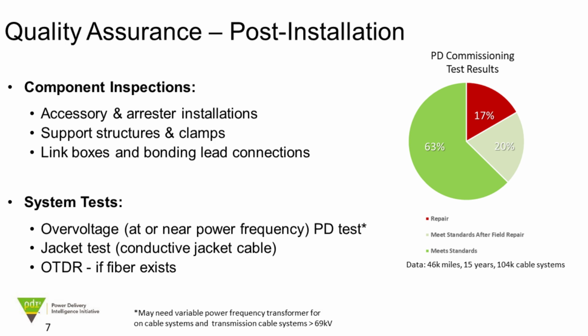Link boxes and bonding leads for cross-bonded and single-point bonded systems. This is typically a transmission application. You need to make sure that those connections are proper. Can't tell you how many times that even after a test is complete and everything looks to be properly installed from a dielectric standpoint, somebody connects up the bonding leads incorrectly. That's a human process. It can happen. The system's not going to survive for its design life. So making sure we have component inspections.